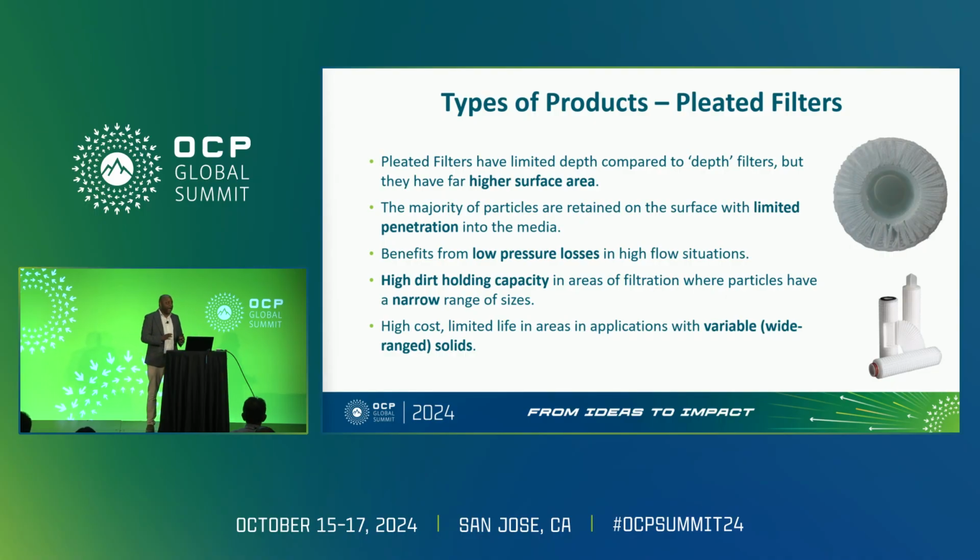But if you find that your fluid is fairly clean and you know what your particle size distribution is, let's say you've got a narrow particle size distribution, this is the perfect product because in those conditions it will give you great flow through, so you can flow through quite quickly through the filter, and also the clean DP will be quite low. So within the right conditions, perfect filter, and absolutely worth the higher price that you would normally pay in terms of difference between that and a depth filter.